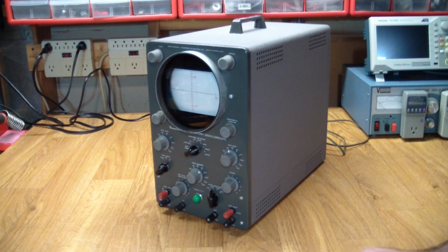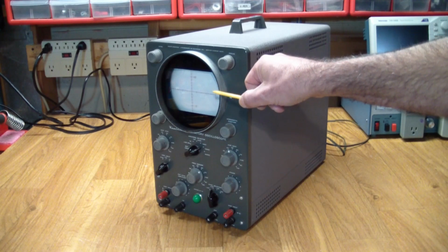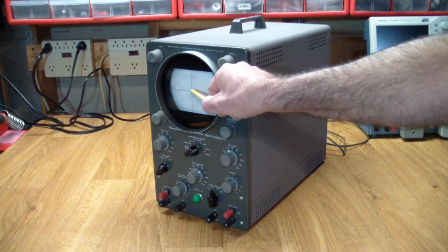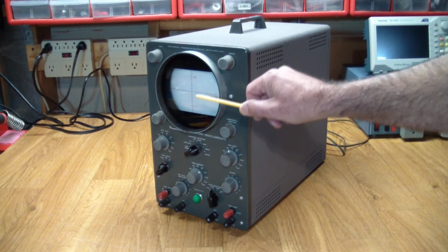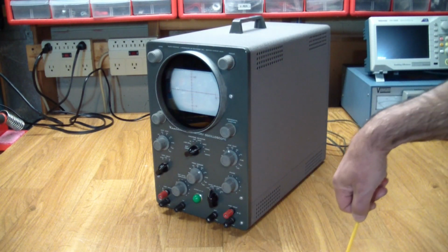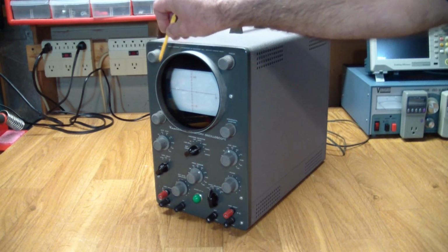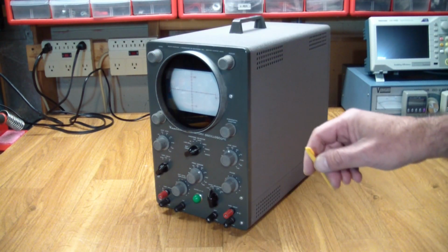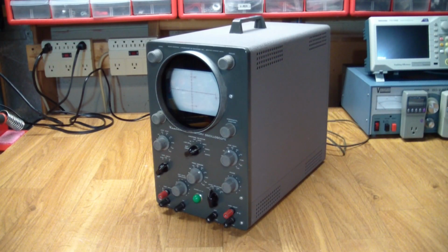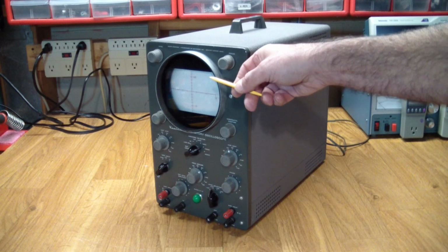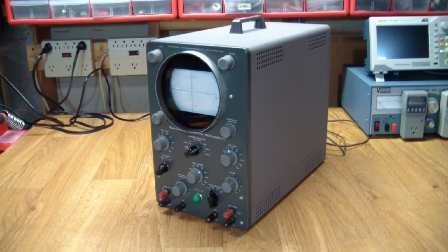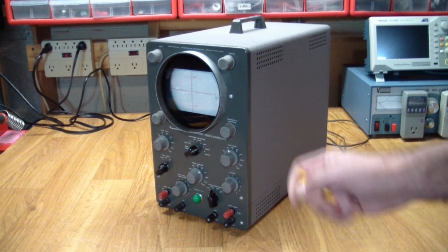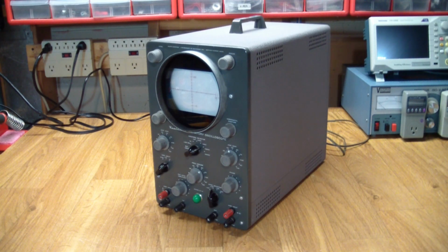It's pretty bare bones. The screen isn't really calibrated, and it's a spherical tube. So if you don't have your eyes level with the center line, it'll look like the trace is curving up on the sides, and I'll show you that later, but that's the so-called parallax effect because of the spherical shape of the tube. That was a characteristic of the older tubes till Tektronix came out with their flat CRT technology that virtually eliminated the parallax effect.